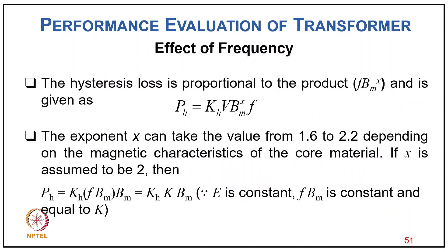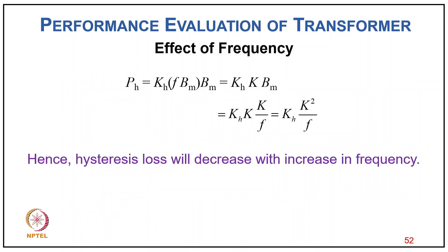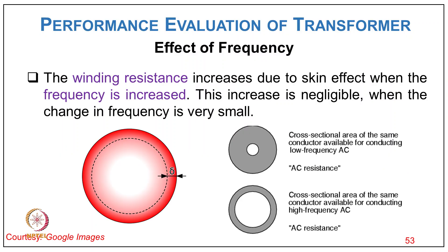The hysteresis loss is proportional to Bm^x × f, where x ranges from 1.6 to 2.2 depending on magnetic characteristics. If x is assumed to be 2, then Ph = Kh × f × Bm², and since f×Bm = k (constant at constant voltage), Ph = Kh × k × Bm = Kh × k²/f. Hence hysteresis loss decreases with increasing frequency when voltage is held constant.